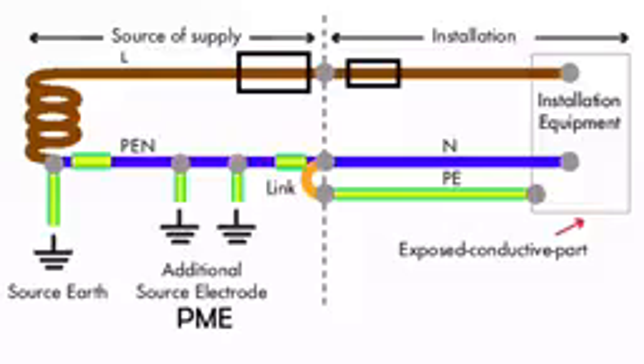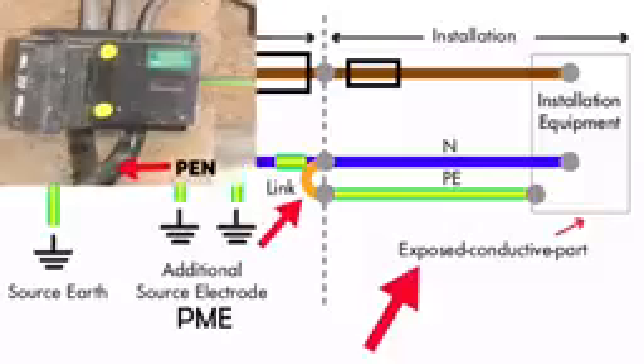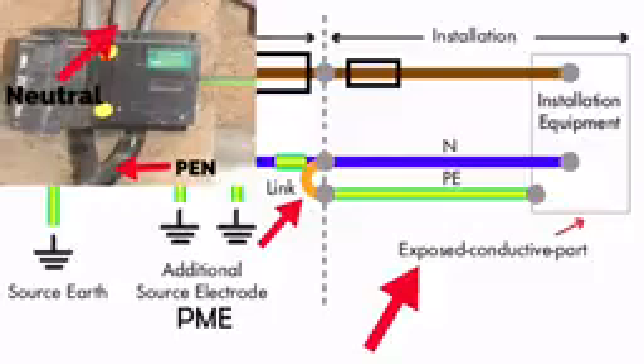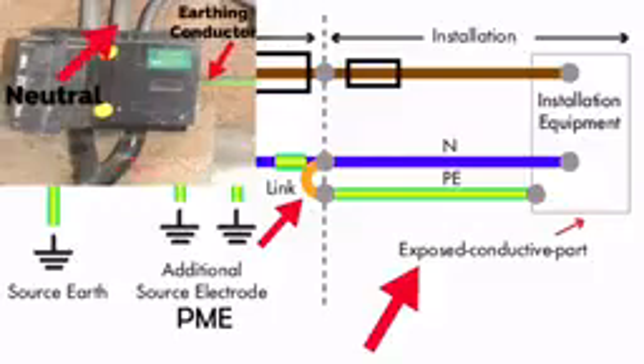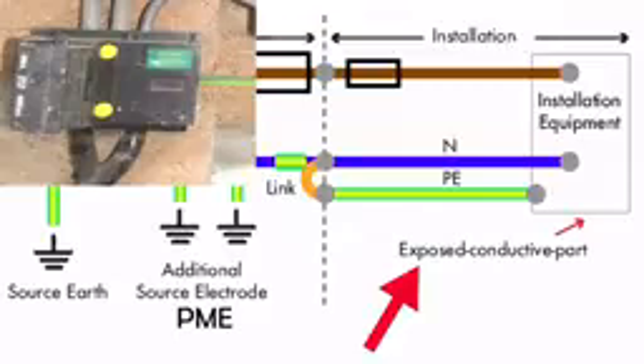The neutral and earth are separate for the installation. This occurs in the cutout. The PEN conductor comes in, and a separate neutral and separate earthing conductor come out from the same position. The exam likes to say these are connected together via a solid link.